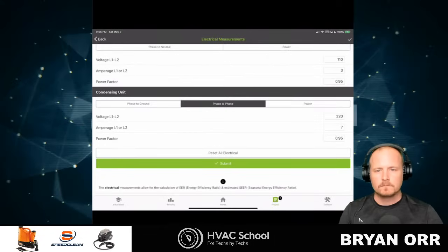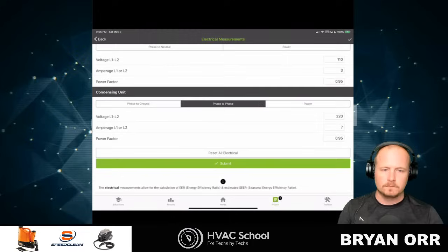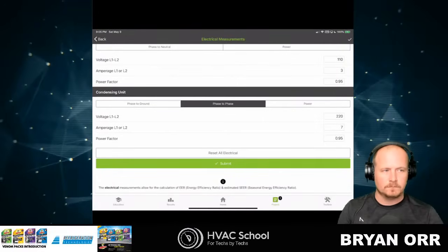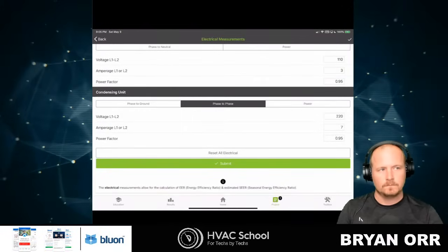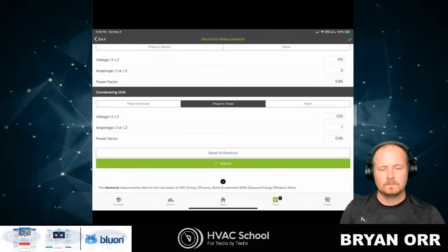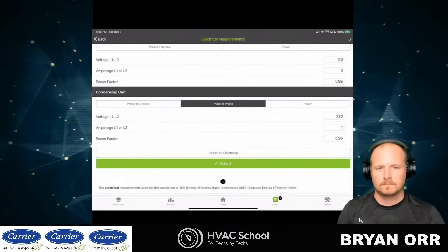I'm seeing more and more of them at 1 now that I got the Redfish meter. Everybody used to say 0.95, 0.9, 0.96, whatever, and I'm seeing so many at 1, if you have a good cap on there. It's ridiculous. So I tend to use that more than anything. But then you can just input it's either phase to ground or phase to phase or power directly, and if you're using the Redfish meter, it pulls in all of them at once, one measurement, one click.